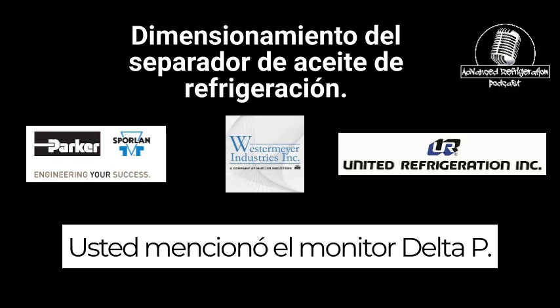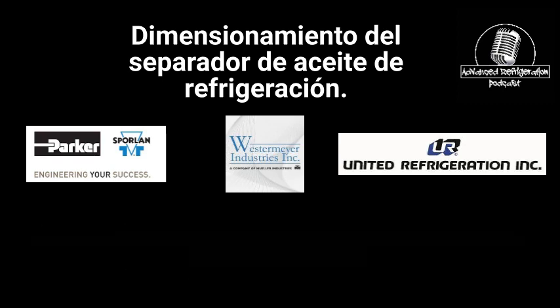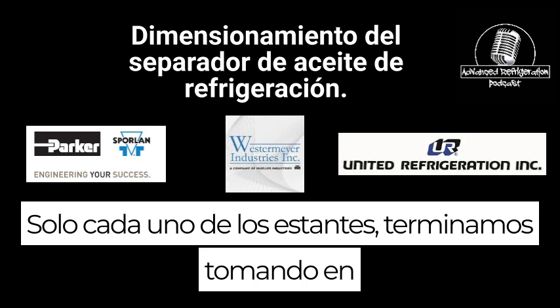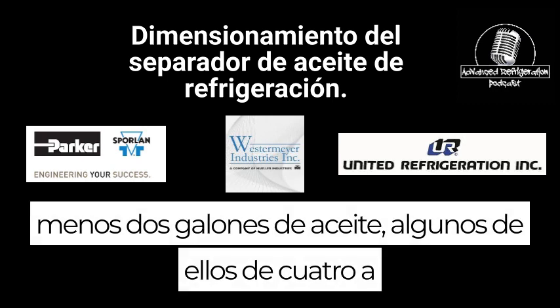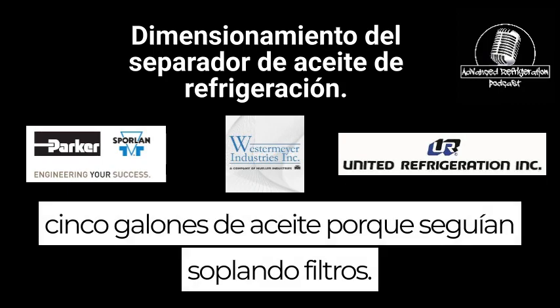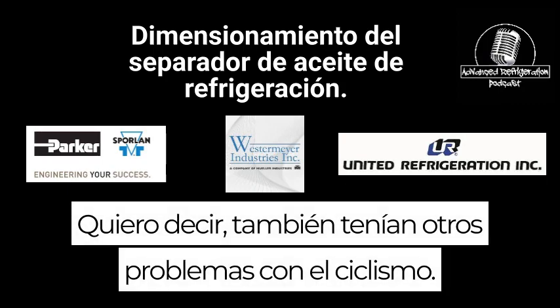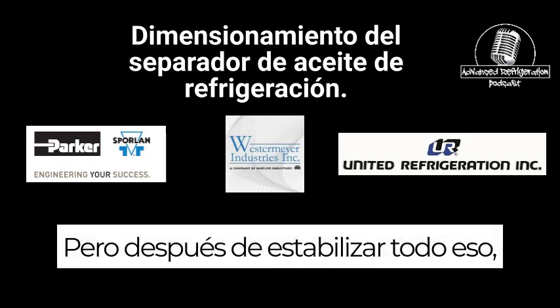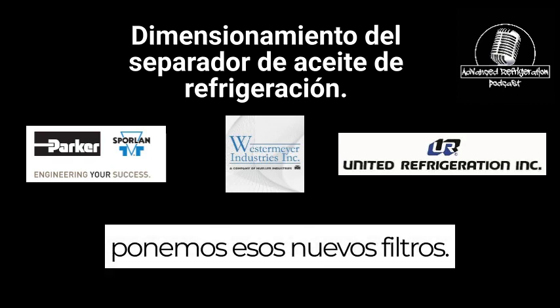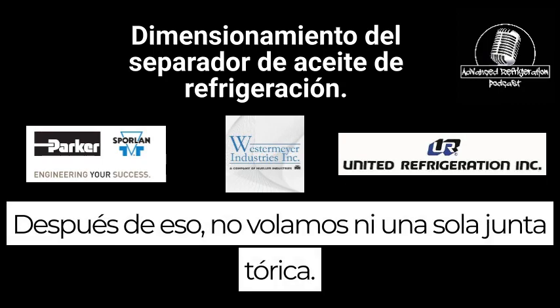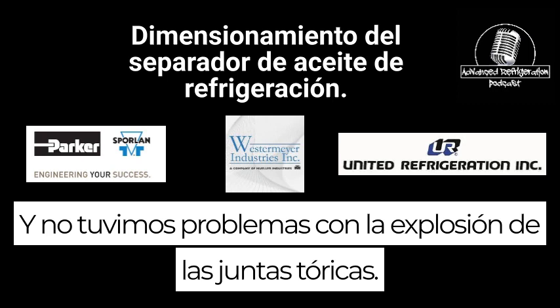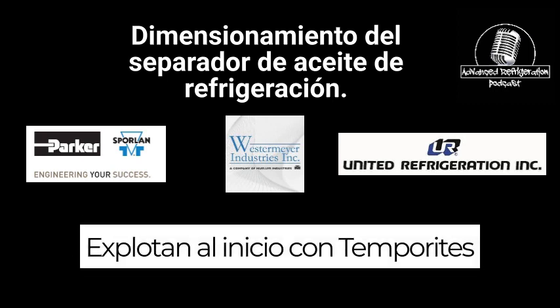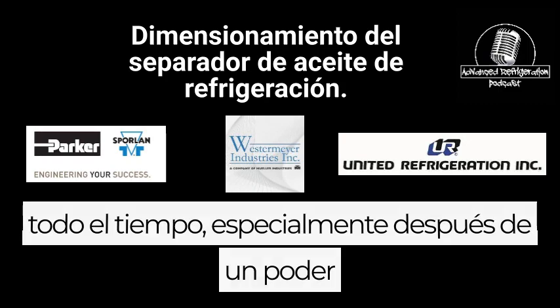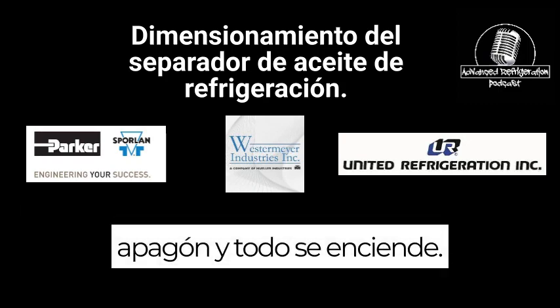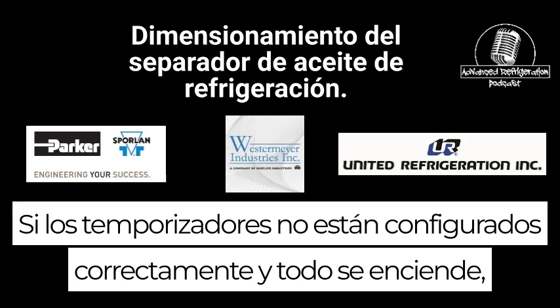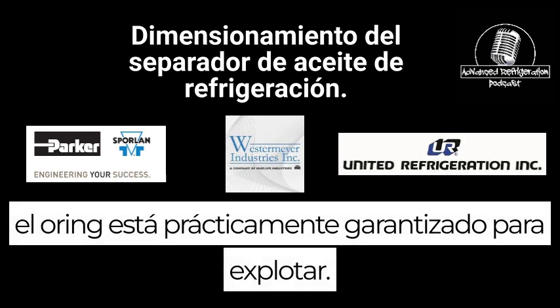You mentioned the Delta P monitor. That one does work for CO2 just as well as a regular one. When we bled the racks, we ended up taking at least 2 gallons of oil out, some of them 4 to 5 gallons, because they kept blowing out filters. I mean, they had other issues too with cycling, but after we stabilized all that and put those new filters in, we didn't blow a single O-ring after that. They blow out on startup with Temprites all the time, especially after a power outage when everything comes on. If timers aren't set right and everything comes on, the O-ring's pretty much guaranteed to blow.